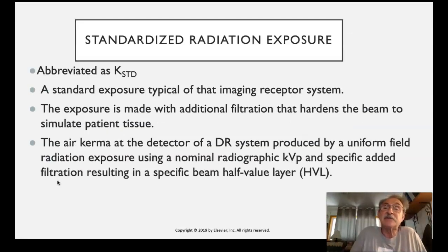The standardized radiation exposure is that which we would expect for a typical image receptor system. What is its baseline response to radiation? This exposure is made with additional filtration that hardens the beam to simulate patient tissue. And so this becomes a standard number, part of the algorithm when we calculate exposure index.